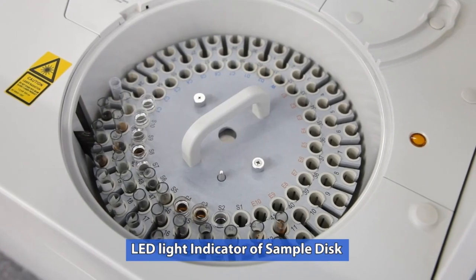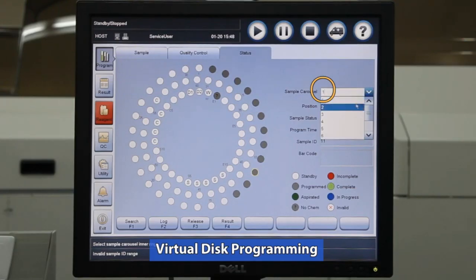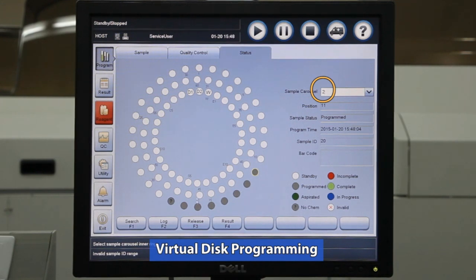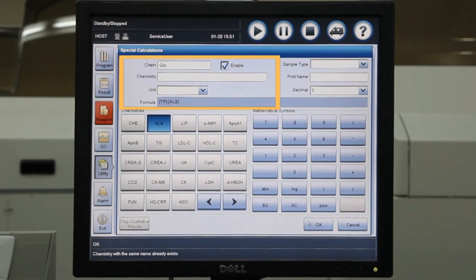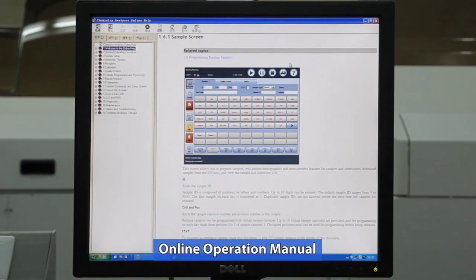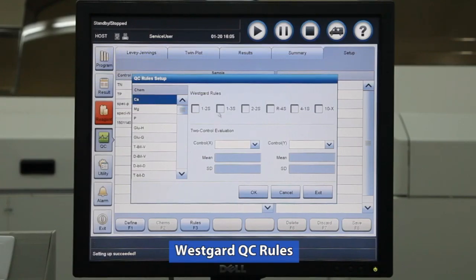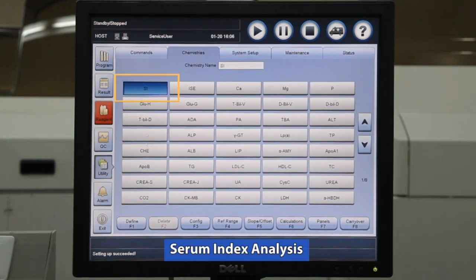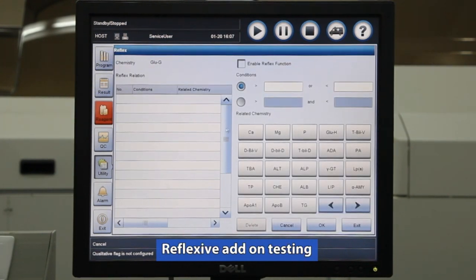Additional software features include: an LED indicator of potential access to the sample disk, virtual sample carousel programming, customisable calculation chemistries, an online operation manual, Levey-Jennings charts, Westgard QC rules, serum index analysis, and reflexive add-on testing.